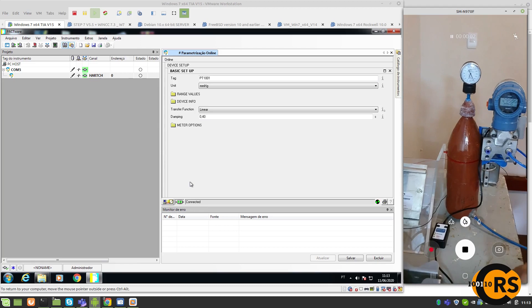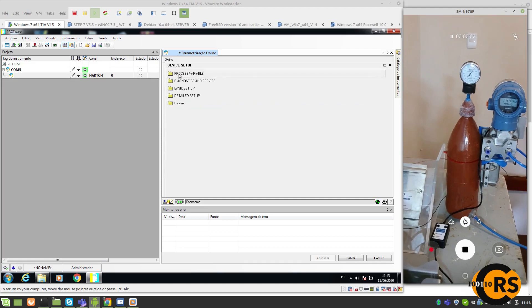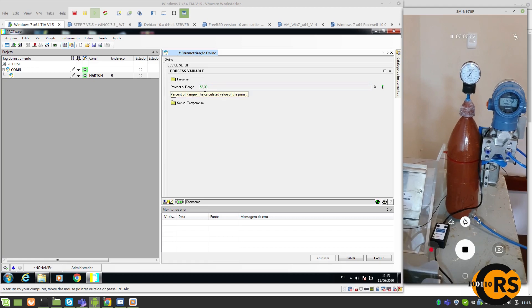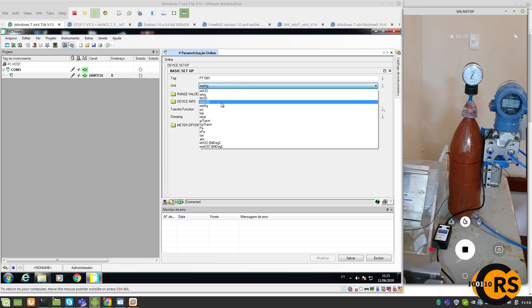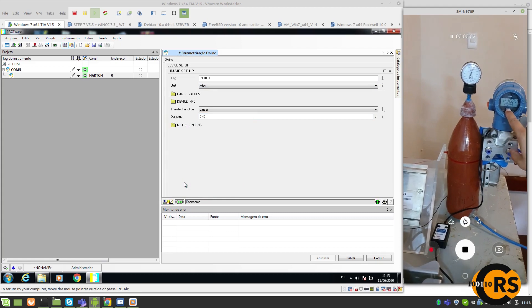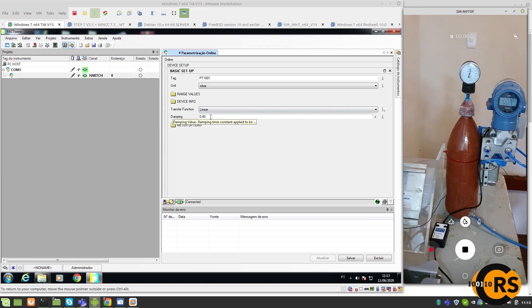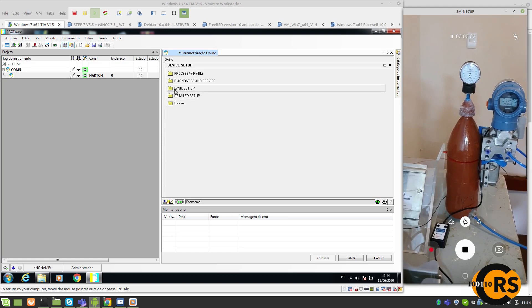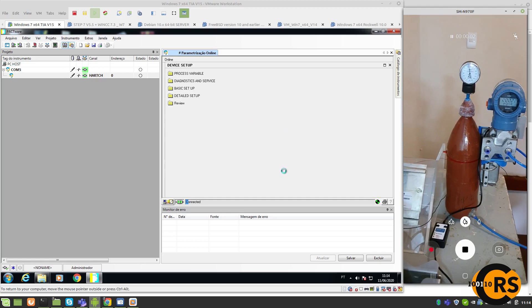Now it's decreasing — I'm going to decrease the pressure a bit. You can see here the device process variable. I'm going to go back to millibar because I'm using this device in my classes. Okay, now it's back to millibar again. This is the damping — the response time to changes of the process variable. I'm going to maintain it at 400 milliseconds. You can also see the process variable diagnostics and review the basic device parameters — a very nice application with HART communication.